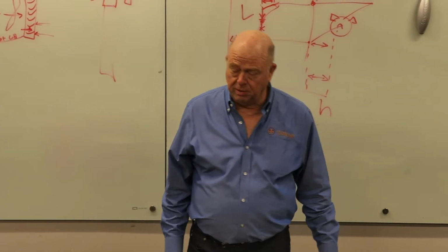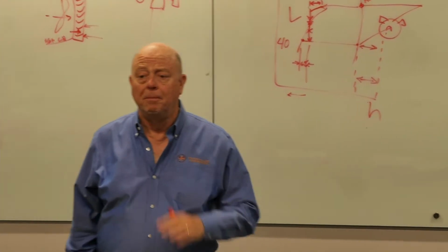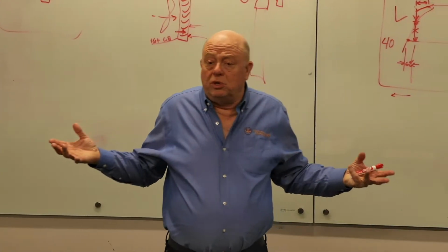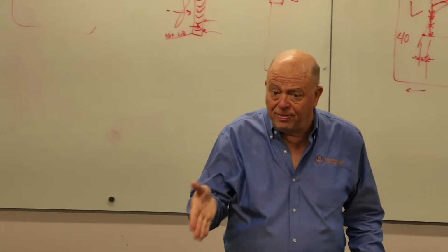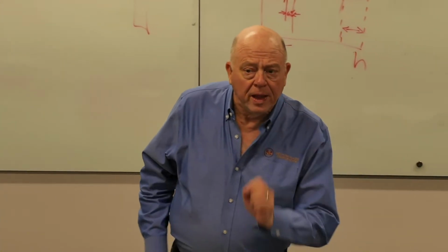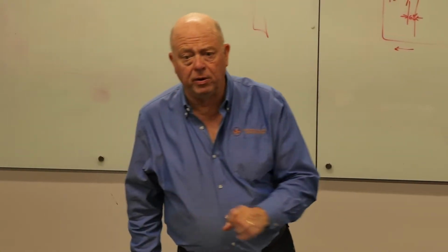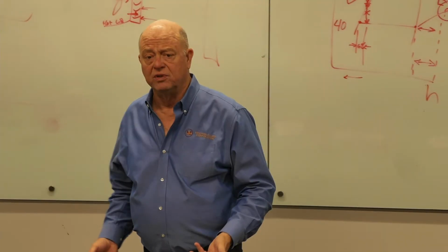We did replace some compressors and there were some issues, but it wasn't as bad as you would assume it would be, and that's because we had that 24/7 load. And that's why sometimes you can get away with buried refrigerant lines for a 24/7 facility.